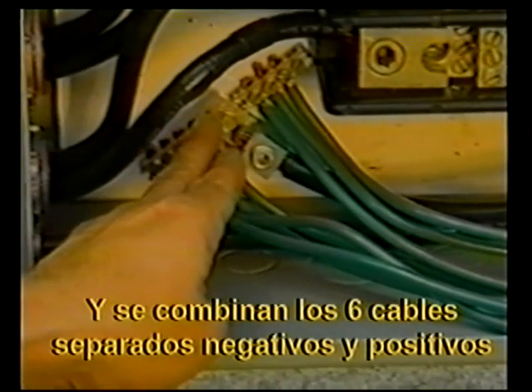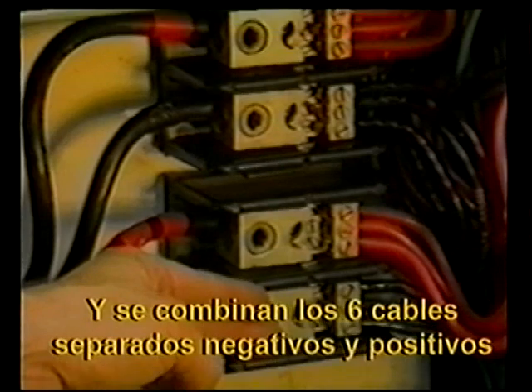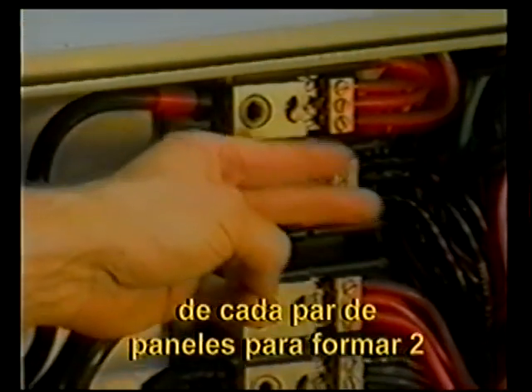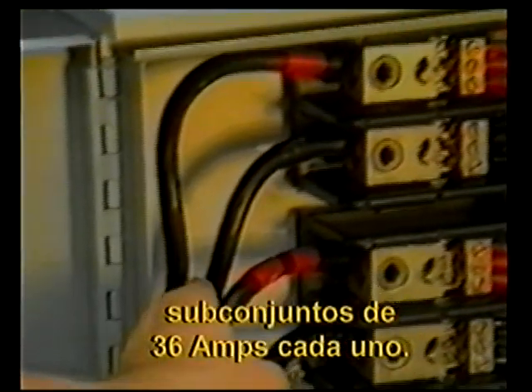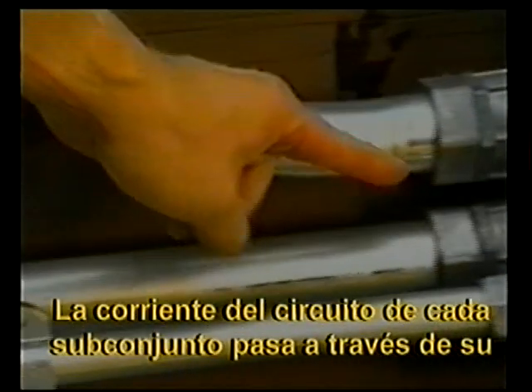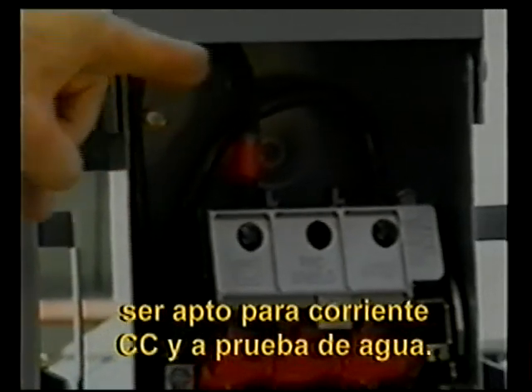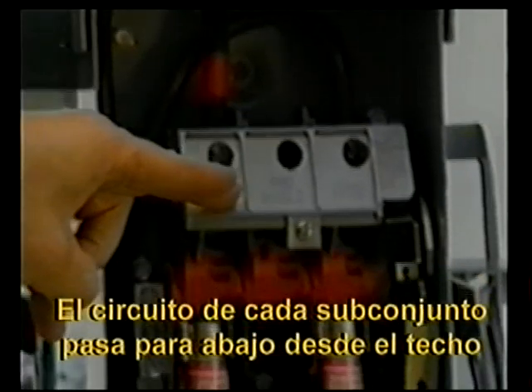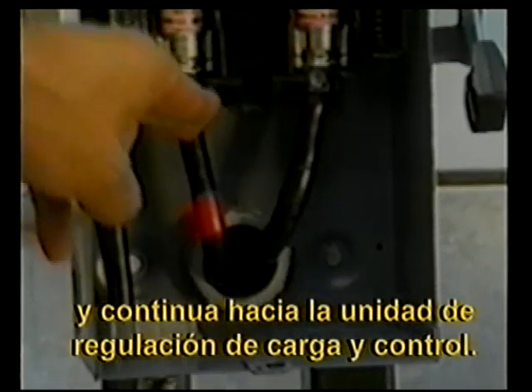And the 6 separate positive and negative wires from each pair of panels are combined to form 2 subarrays of 36 amps each. The current from each subarray circuit passes through its own disconnect switch, which should again be rated for DC current and should be water resistant. Each subarray circuit then passes down through the roof and onto the charge regulation and control unit.